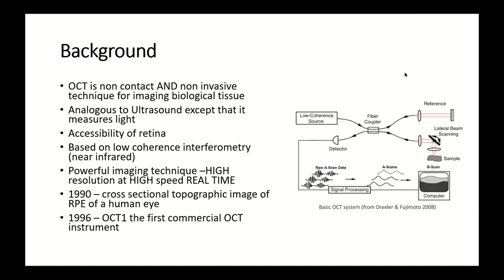Here you can see a basic illustration of the OCT principles. A low-coherent source of light is emitted and then split by a beam splitter into a reference beam and a probing beam. The probing beam is directed towards the retina, and when the light reflects back it passes to the detector. Similarly, the reflected light from the reference beam is collected, and all information is then stored and analyzed in the computer.